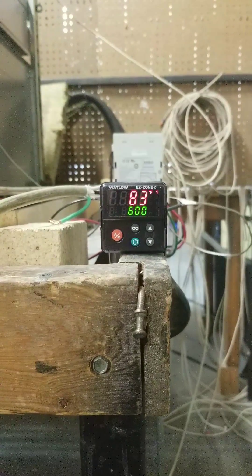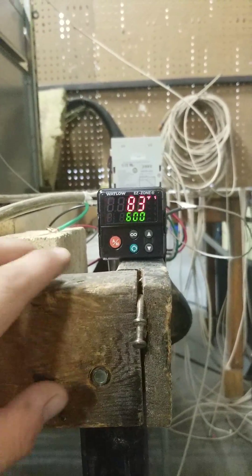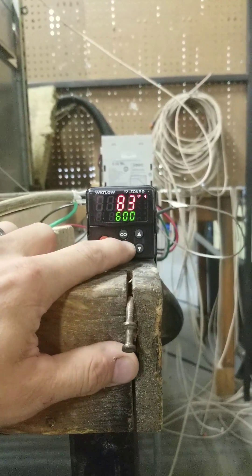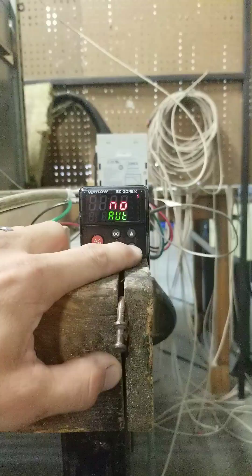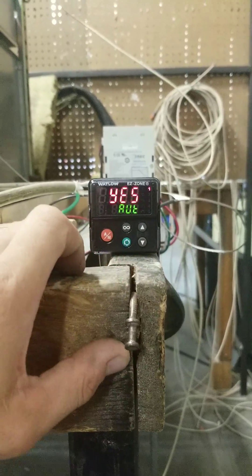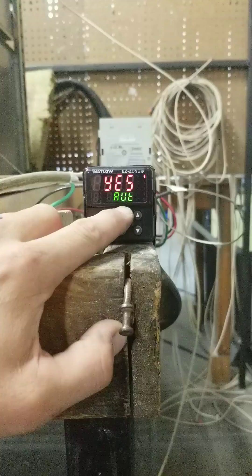Setting Auto-Tune on a Watlow EZ-ZONE. Press the green button. This shows Auto-Tune No. Put the down arrow once — it'll say Auto-Tune Yes. When you're done, press the Infinity key.